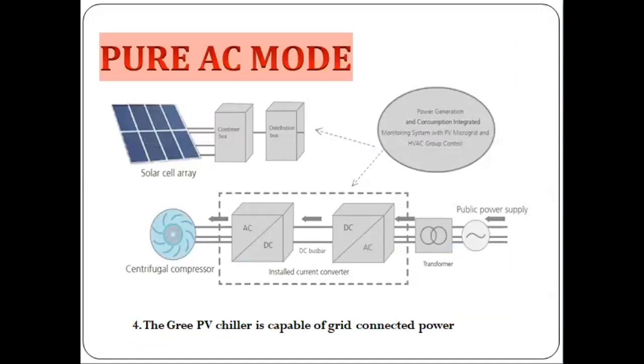Number 4, the GREE PV chiller is capable of grid-connected power. When the control panel displays pure AC mode, it indicates that the unit draws power from the power line or utility company instead of the PV system. In this mode, the PV system is entirely isolated and the unit becomes a typical direct-driven inverter centrifugal chiller.